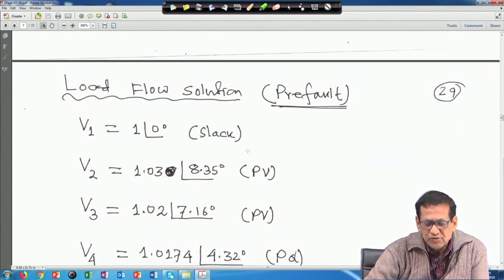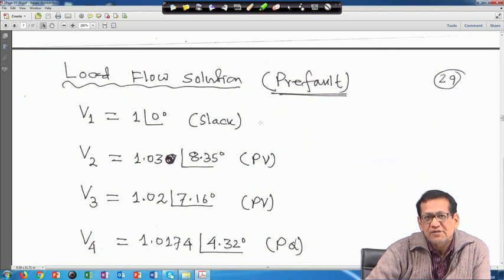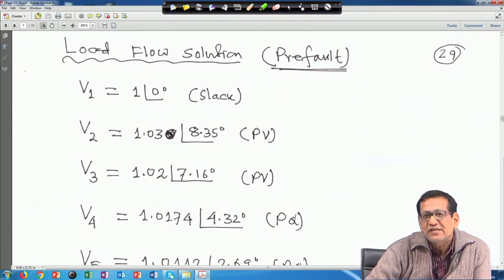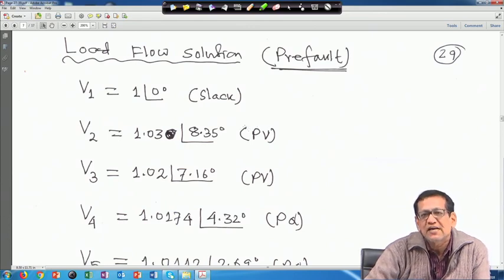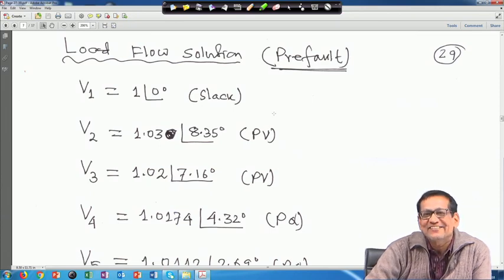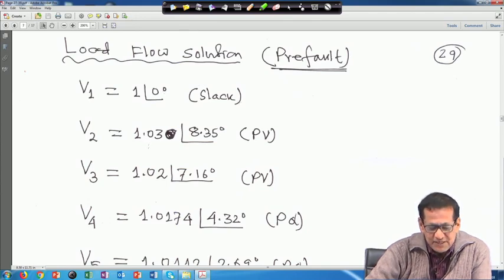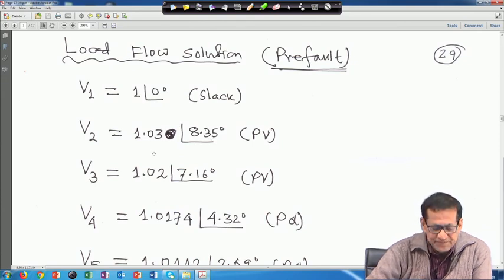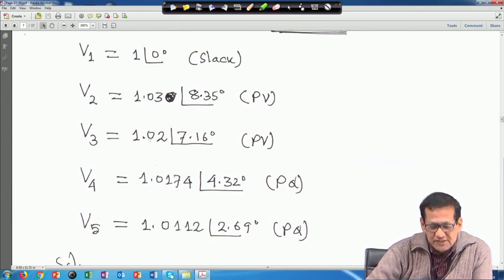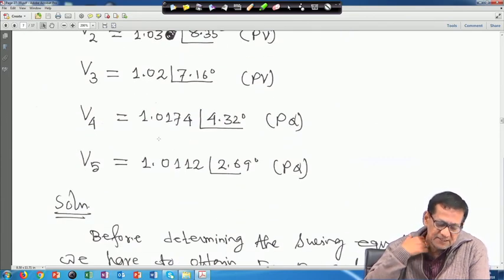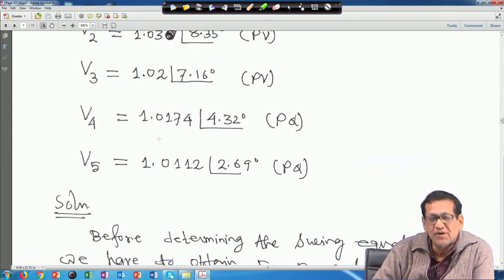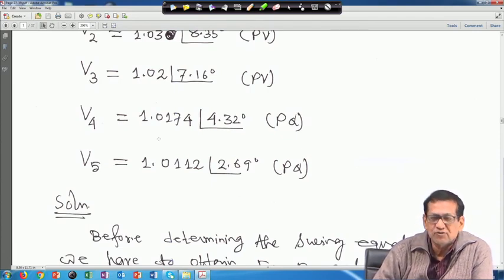These are the load flow solutions for the pre-fault condition. You run the load flow and get these values — for assignment or exam purposes this solution will be provided. V1 = 1∠0° (slack bus), V2 = 1.03∠8.35° (PV bus — voltage magnitude specified), V3 = 1.02∠7.16° pu (PV bus), V4 = 1.0174∠4.324° and V5 = 1.0112∠2.69° (PQ buses). These are the load flow solutions.